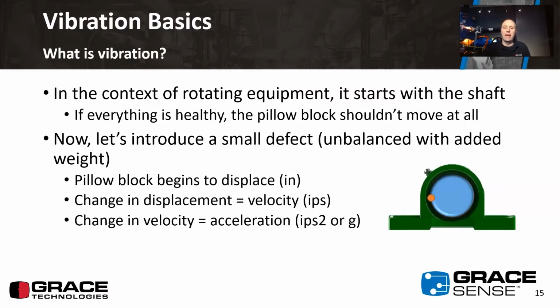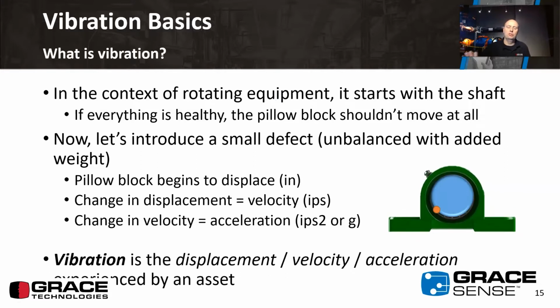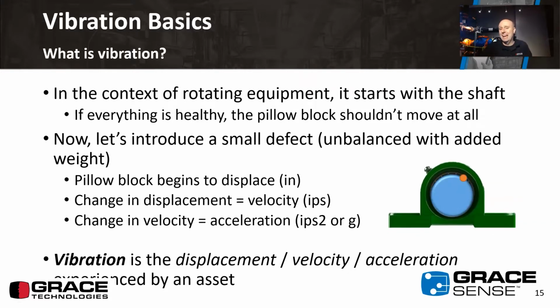We can also look at that change in displacement in terms of velocity. So that's the speed with which this thing is actually moving, right? That's inches per second. And then we can look at the change of velocity, which is an acceleration measurement, and that we typically monitor in inches per second squared, or G. So when we talk about vibration, we're talking about any one of these three things: the displacement, the velocity, or the acceleration that's experienced by an asset, in this case, this pillow block bearing.